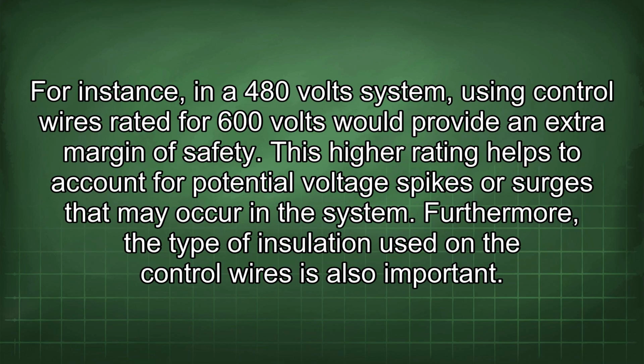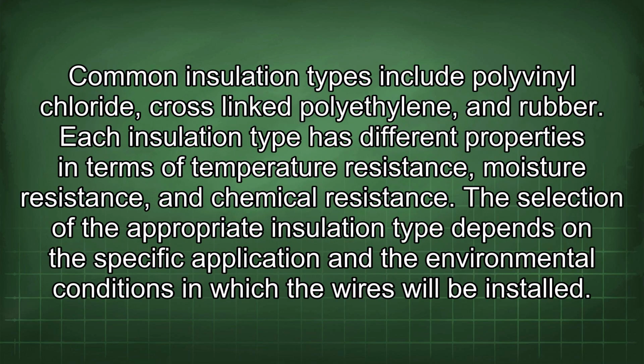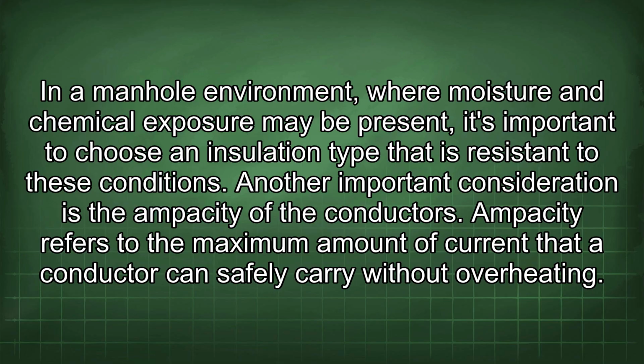For instance, in a 480 volt system, using control wires rated for 600 volts would provide an extra margin of safety. This higher rating helps to account for potential voltage spikes or surges that may occur in the system. Furthermore, the type of insulation used on the control wires is also important. Common insulation types include polyvinyl chloride, cross-linked polyethylene, and rubber. Each insulation type has different properties in terms of temperature resistance, moisture resistance, and chemical resistance. The selection of the appropriate insulation type depends on the specific application and the environmental conditions in which the wires will be installed. In a manhole environment where moisture and chemical exposure may be present, it's important to choose an insulation type that is resistant to these conditions.